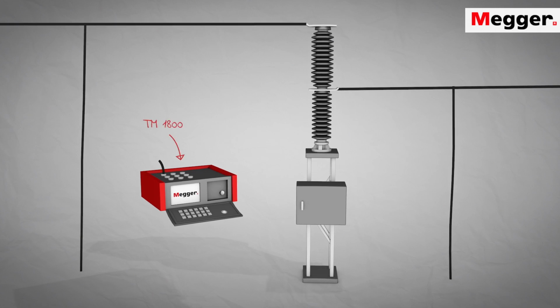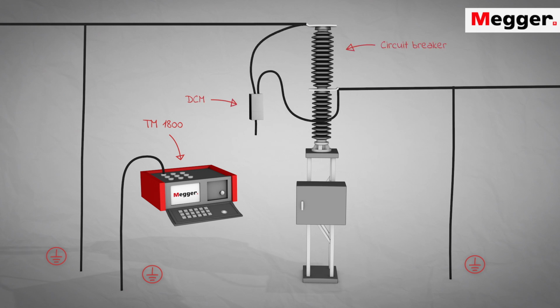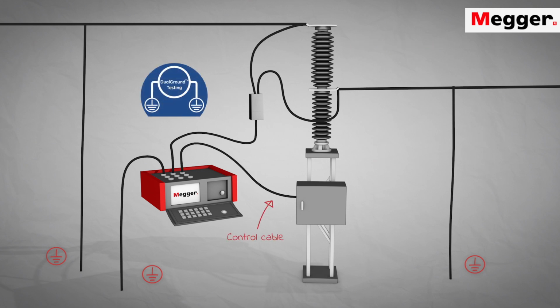Start by connecting the TM1800 to ground. Connect the DCM cables to the circuit breaker. Connect the control cables to the circuit breaker strip and close coil circuits. The test can now be performed safely.